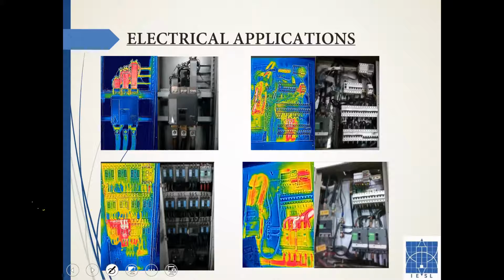These are some classic images we've captured. Keep in mind there are many components in a power distribution system - there are breakers, and on either side of the breaker, here it's a cable and on the upside it's a bus. So there's a subject called evaluating your connection. In NETA, the InterNational Electrical Testing Association standards, they state the maximum temperatures you should have under similar loads.